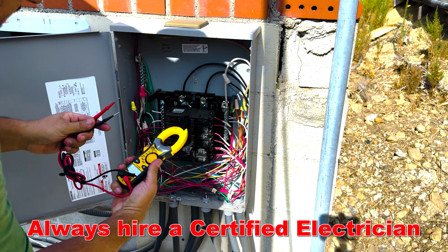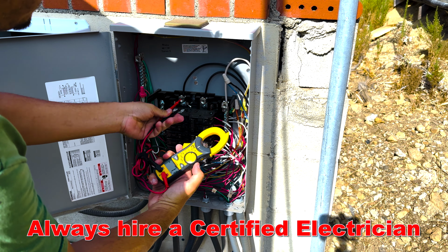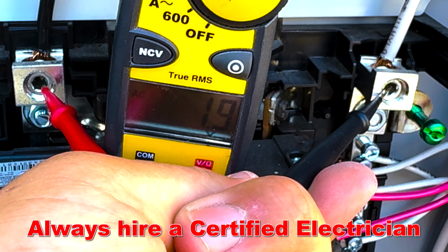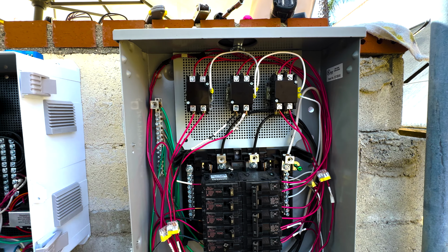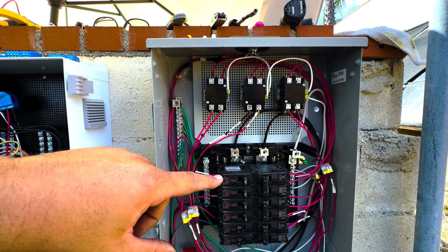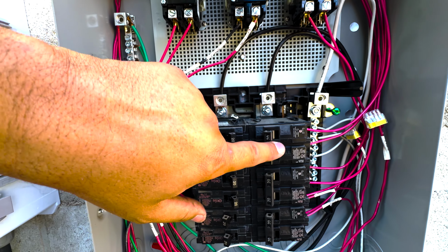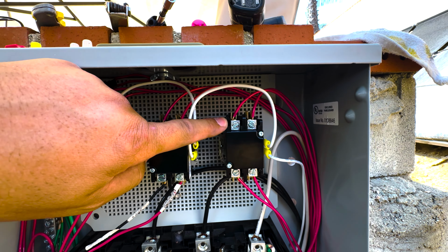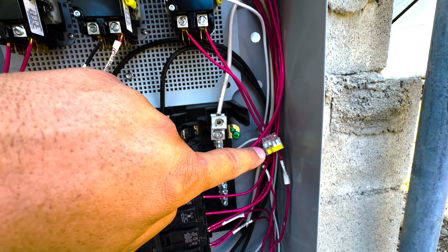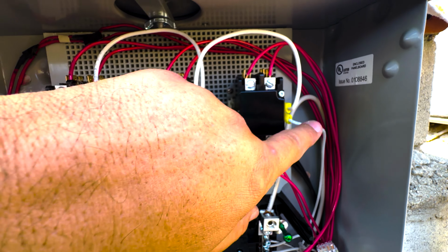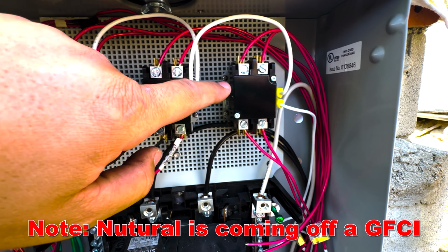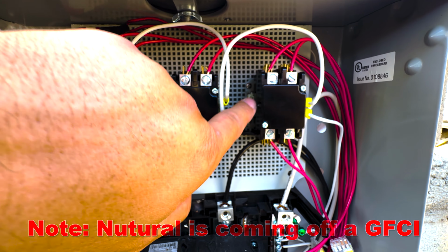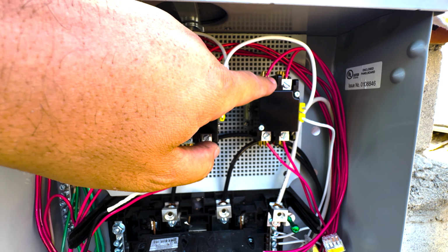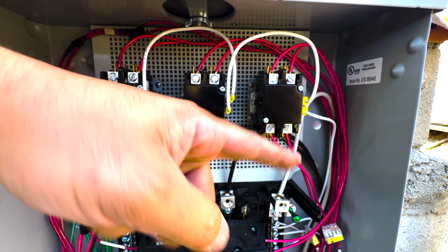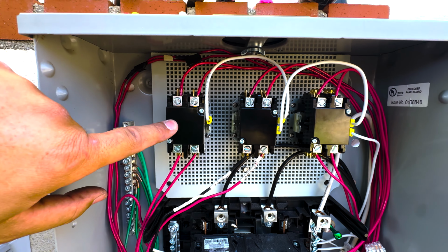Let's confirm power is actually off with a multimeter. I've got it set to AC. We put it on the two legs up here, and we're not getting 120. So power's off. I installed the 3 contactors on top of the breakers, and what each one of them is doing is the same as this one right here. I've got a 220 breaker supplying 2 lines up to the top of the contactor right here. Then on the other side of the contactor down here, these lines run out to the actual pump. I have a neutral wire powering this side coming off of the bank. Then on this side, I will switch. When the switch gets activated here, it applies the power between here and here, activating the contactor and turning on the pool pump. And I did the same thing for the other 2, the blower and the waterfall.